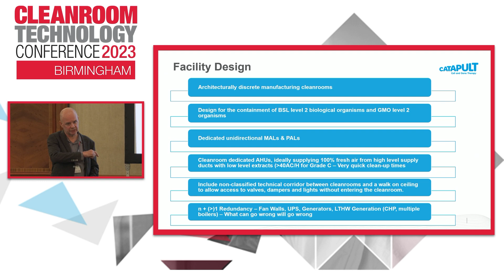So the design needs to be commensurate for the containment of BSL level 2 and GMO level 2 organisms. Typically, if you're looking at working with entities more exotic or pathogenic than level 2, then you enter a different environment entirely. And there's a whole raft of additional controls that will be required. For each of your discrete clean room environments, you want dedicated material and personnel airlocks, and wherever the design can be arranged as such, they are best to be unidirectional only. So there's a single route, no reversal of flows for people, waste, or materials.